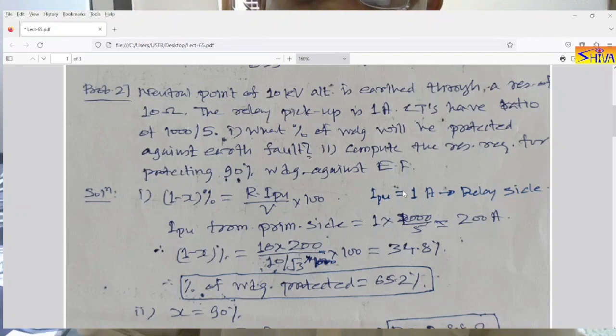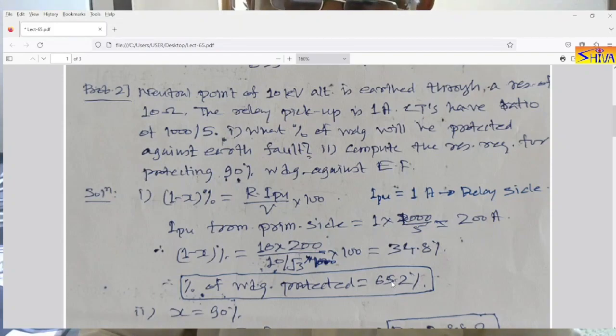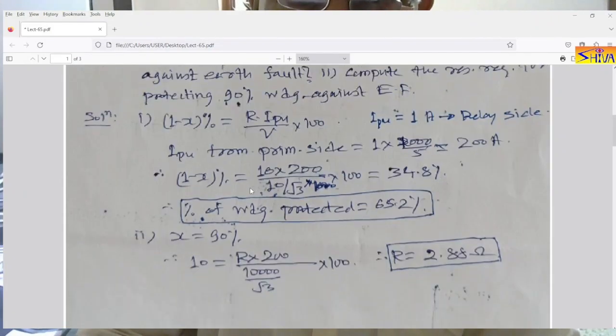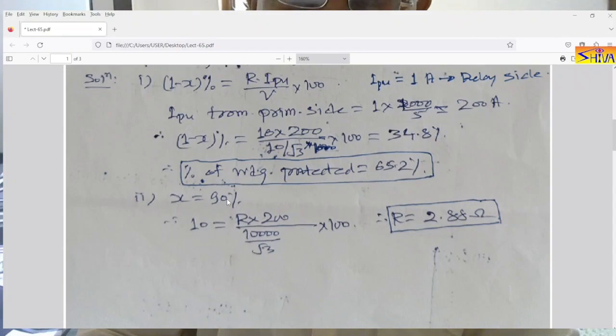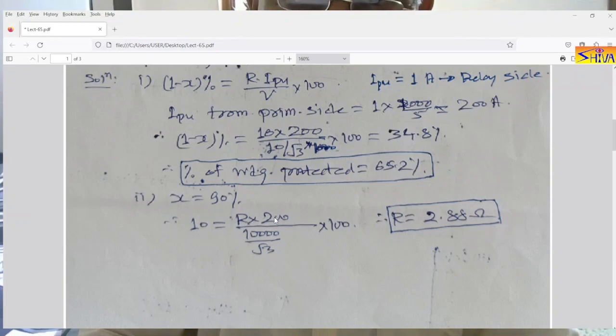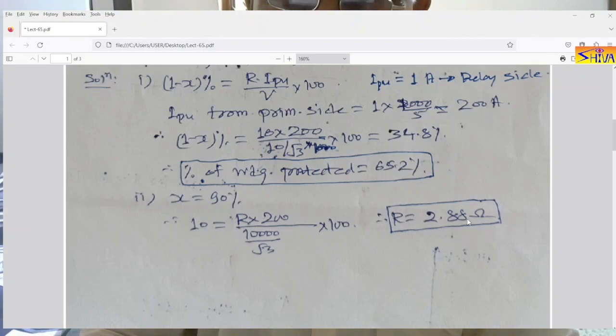For the second part, we need to compute the resistance required for protecting 90% of the winding. So we have to increase the percentage of winding protected from 65.2% to 90%. With x = 90%, the unprotected portion is 10%. Setting up the equation: 10 = R × 200 / (10,000 / root 3) × 100. Solving, R comes out to 2.88 ohms.